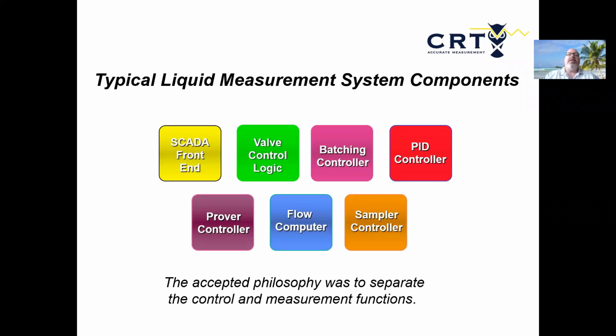So in a typical liquid measurement system, you have all these different components. You've got a SCADA system, which is, let's say, where the controllers are, and they have a front-end system where they're seeing process information come back from the flow computers. You've got valve control logic, which is typically inside of a PLC, so it's opening and closing valves into systems or in and out of tanks and so forth. You've got a batch controller, which is basically controlling how much is coming through on a particular system. You've got PID controllers, so you're controlling flow rates, you're controlling pressures, you're controlling back pressures on a system.